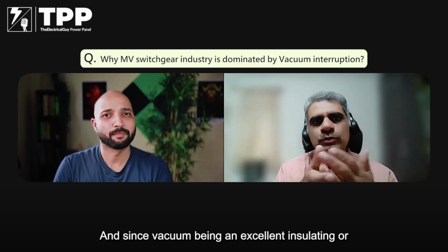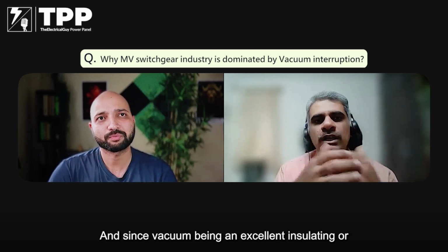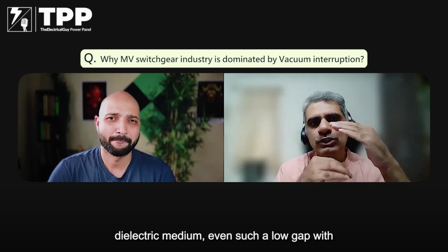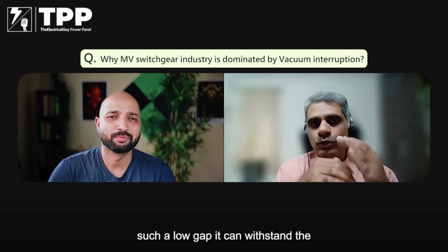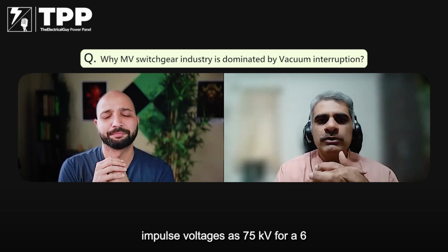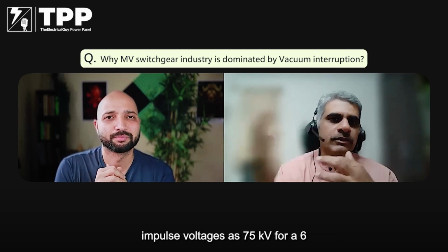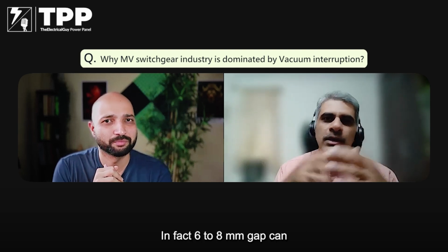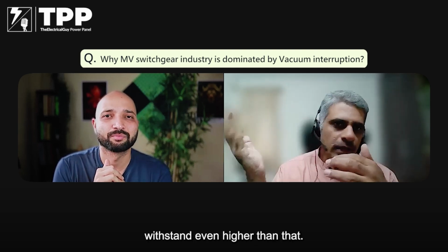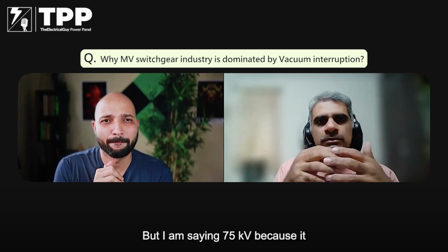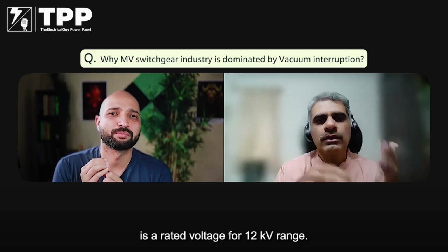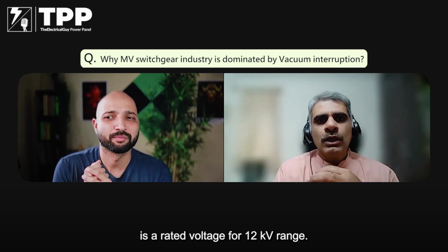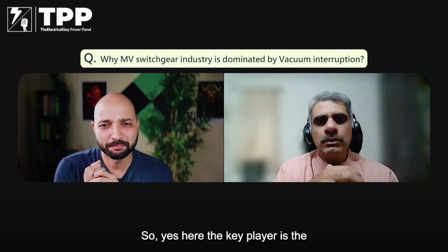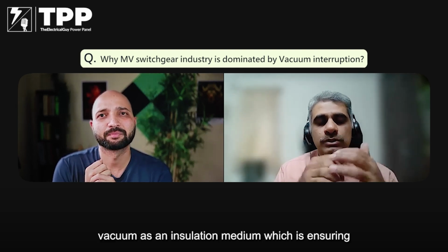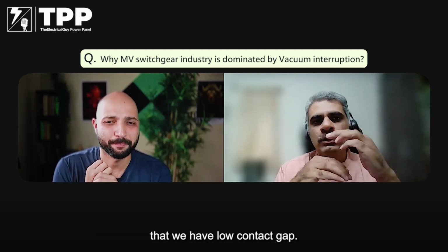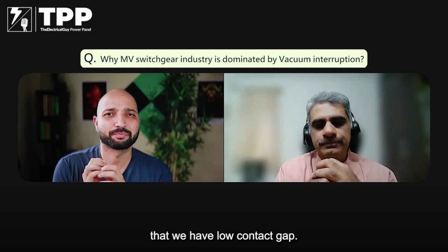And since vacuum is an excellent insulating or dielectric medium, even with such a low gap, it can withstand impulse voltages as high as, say, 75 kV for a 6 to 8 mm gap. In fact, a 6 to 8 mm gap can withstand even higher than that. But I'm saying 75 kV because it's the rated voltage for the 12 kV range. So yes, here the key player is the vacuum as an insulation medium, which is ensuring that we have a low contact gap.